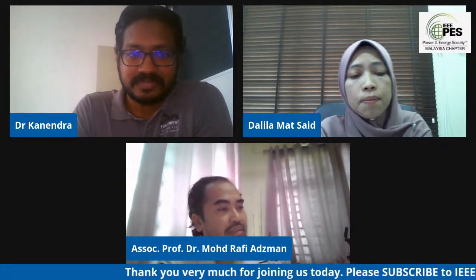For the first detection method, we use a positive sequence value because it only wants to differentiate between the normal and fault conditions. If a fault occurs, the total fault current will be very high compared with the summation of pre-fault local and remote currents. So using the positive sequence is sufficient to detect.